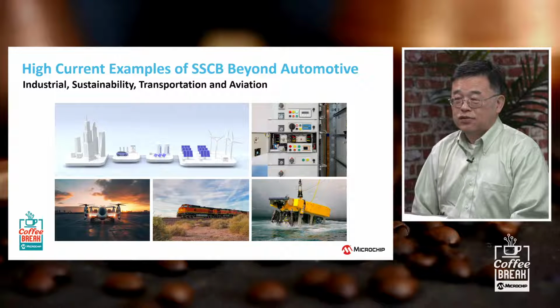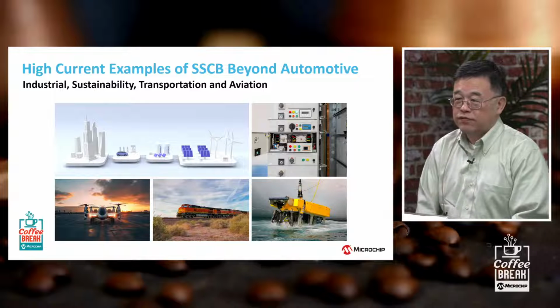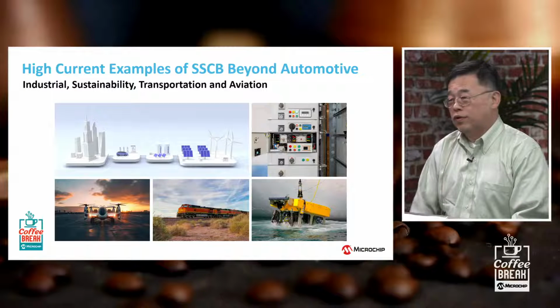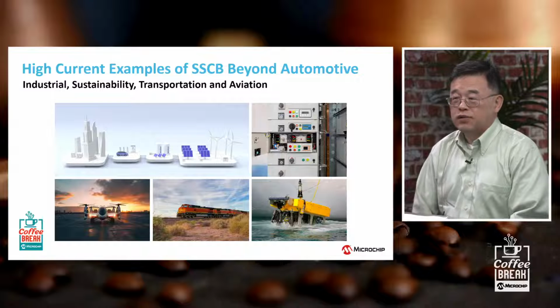As a result, silicon carbide is great for that because it has higher thermal tolerance and higher performance switching, and you can scale, for example, all the way from 650, 700 volts on the low end, up to 3.3 kV and beyond in terms of silicon carbide solutions today. And that also depends on the number of devices and the voltage specification of the system, so it's quite flexible.